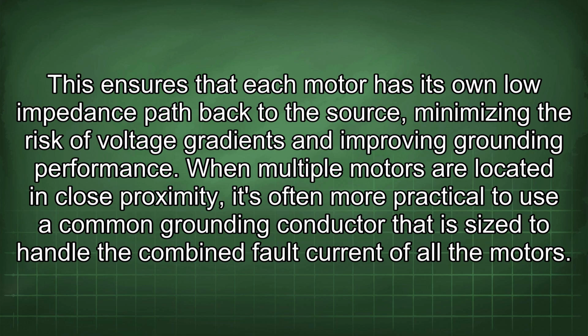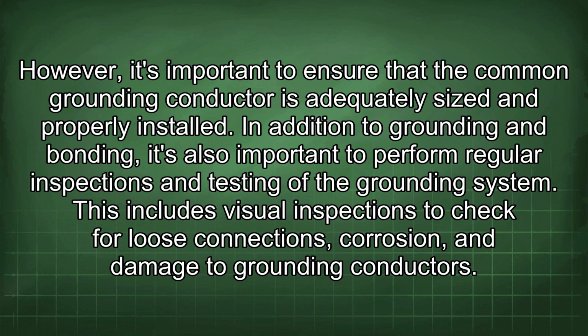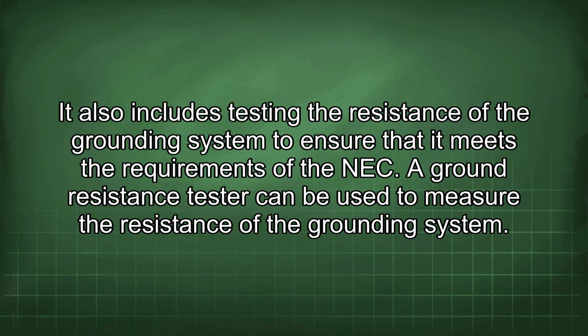When multiple motors are located in close proximity, it's often more practical to use a common grounding conductor that is sized to handle the combined fault current of all the motors. However, it's important to ensure that the common grounding conductor is adequately sized and properly installed. In addition to grounding and bonding, it's also important to perform regular inspections and testing of the grounding system. This includes visual inspections to check for loose connections, corrosion, and damage to grounding conductors. It also includes testing the resistance of the grounding system to ensure that it meets the requirements of the NEC. A ground resistance tester can be used to measure the resistance of the grounding system.